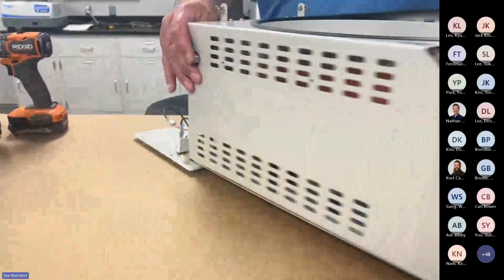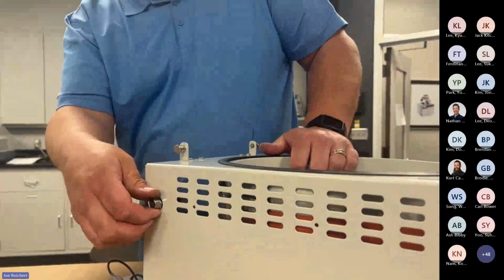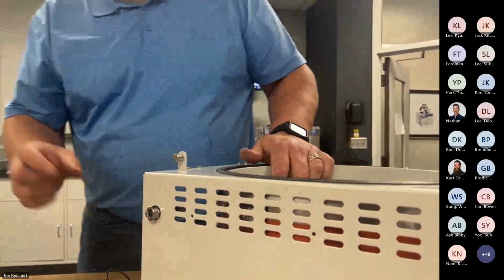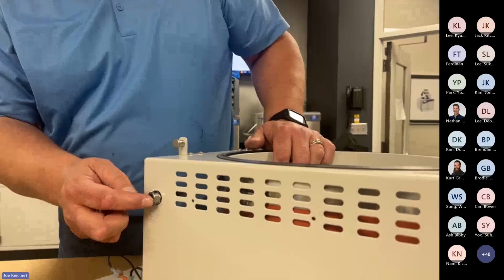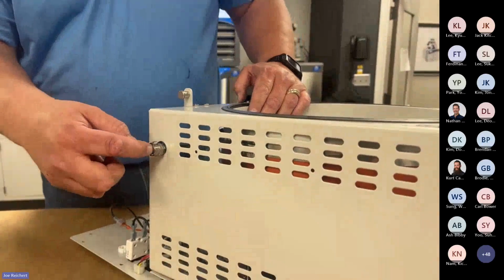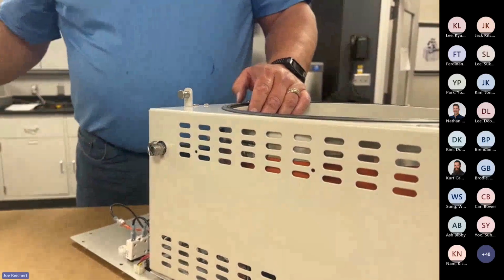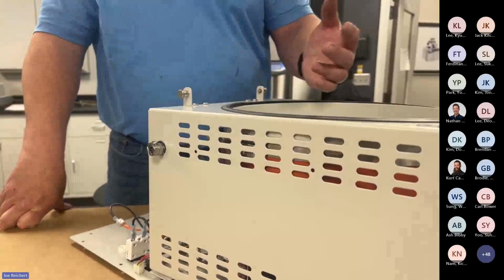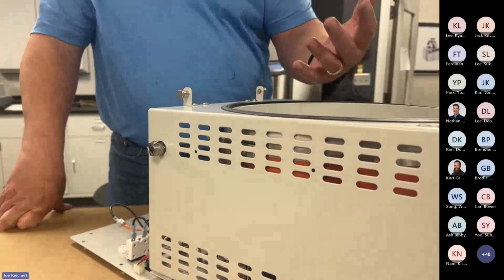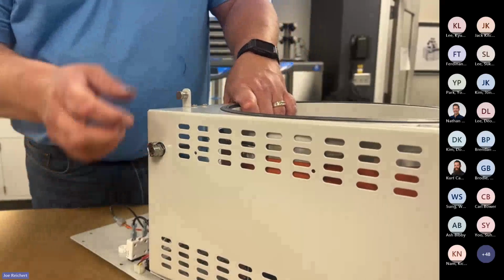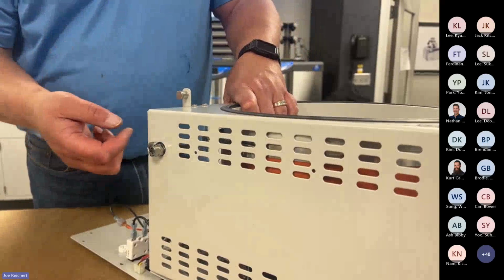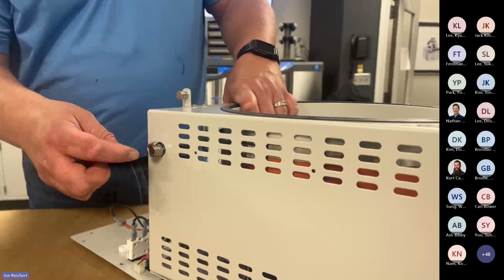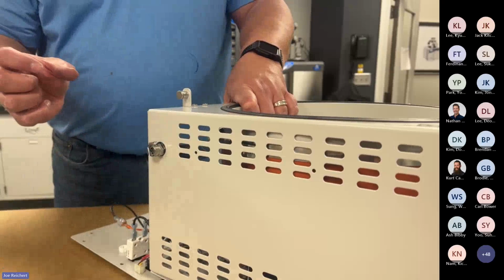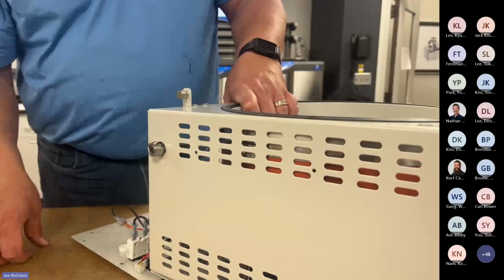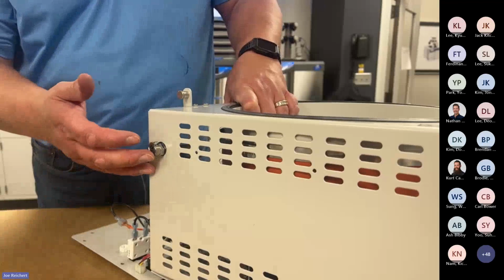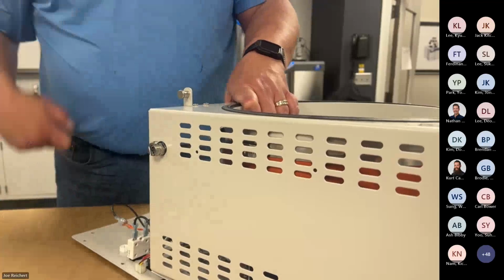Okay. So now the wrapper is going to be able to come off, and you still have this little valve here on the side. This valve here is for measuring vacuum pressure. There's a little hose barb that comes with each unit, and you stick it in here and it opens the valve. I've seen customers have an issue with their drying. They're getting maybe condensation on the lid of the unit, but it's because they're losing vacuum someplace. And I'll ask for pictures of the unit and I'll see the hose barb sticking right in the side. A little small piece, they didn't want to lose it, so they stuck it in there for safekeeping, not realizing that they're opening up a valve and now they're sucking air through that valve, and that hurts your vacuum pressure.